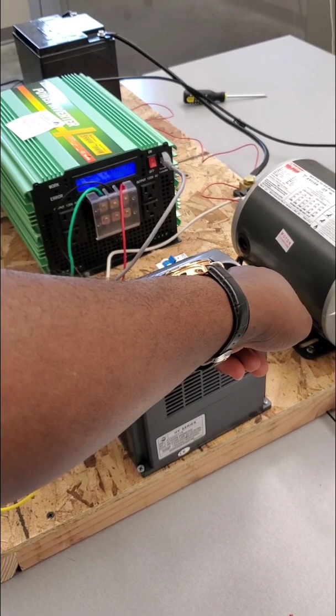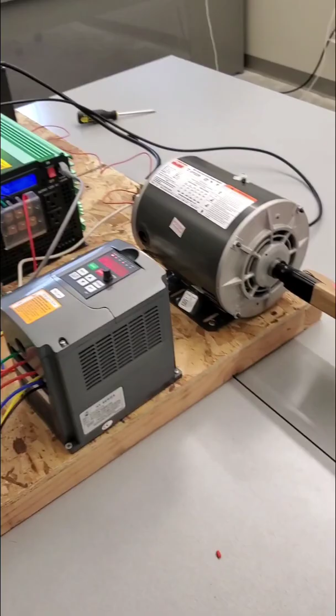Run it. Now you can see the numbers are static. When you are running it, you can check the rotation speed of the motor, the current, the frequency, the revolution. This one is reversed, this one is forward, and then the power. The LED is indicating rotation. If you want to see the frequency at which the motor is running, you use shift. If I press shift, you can see it comes to hertz. So now you can run.